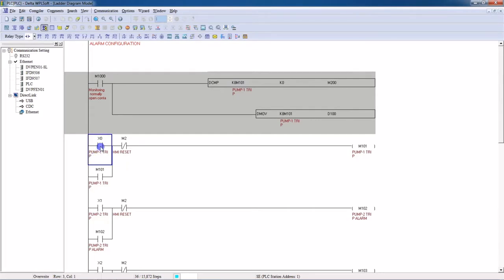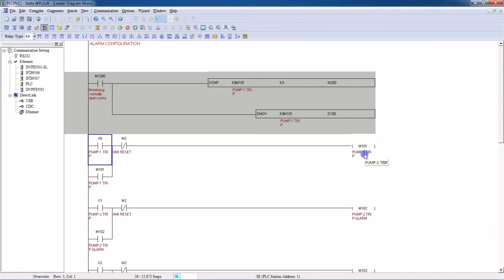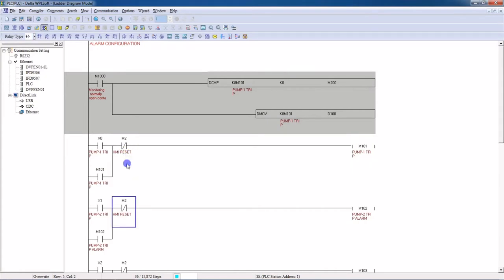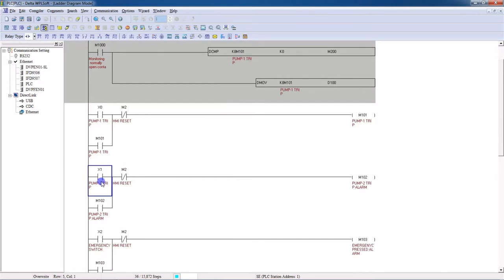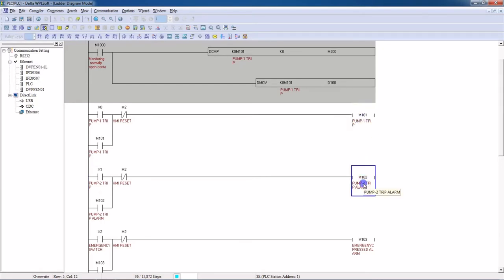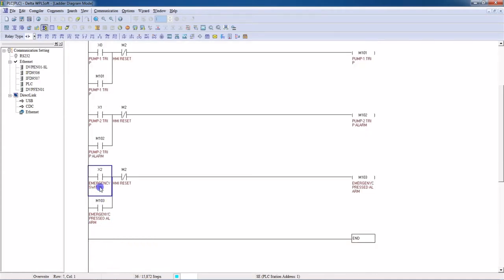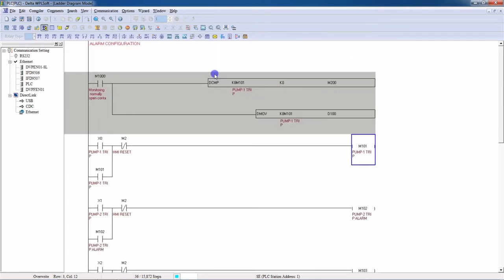My first alarm is pump one trip — this is the pump one trip input feedback X0. If X0 is high, I will turn on M101, so the first alarm is pump one trip. My second alarm is pump two trip — if X1 is present, take the next address, which is M102. The third alarm is emergency switch, so the address will be next: M103. This is our PLC program and we will download it to the PLC.